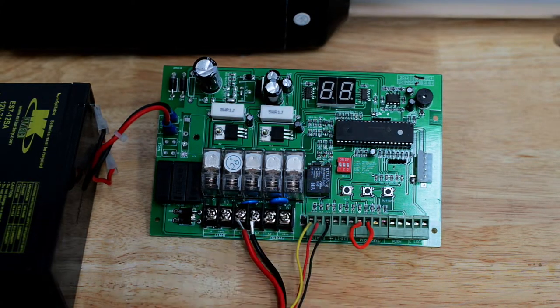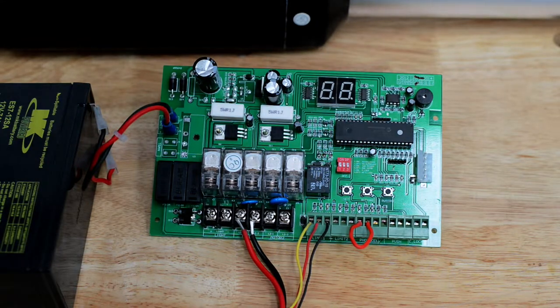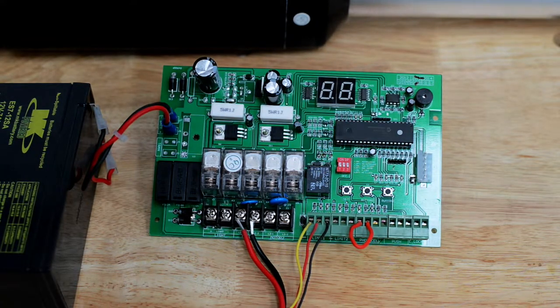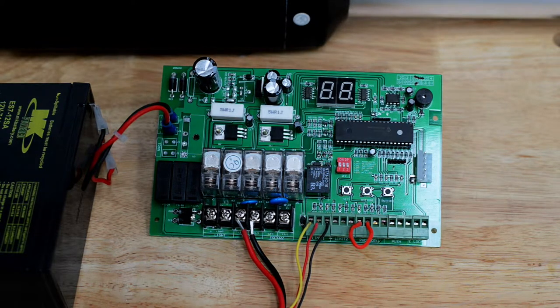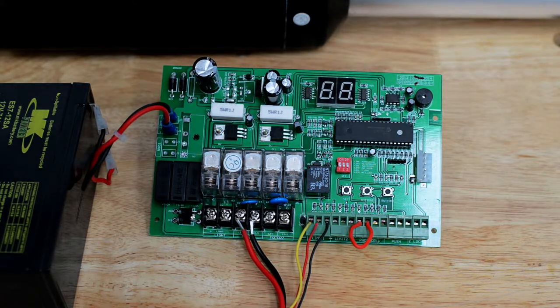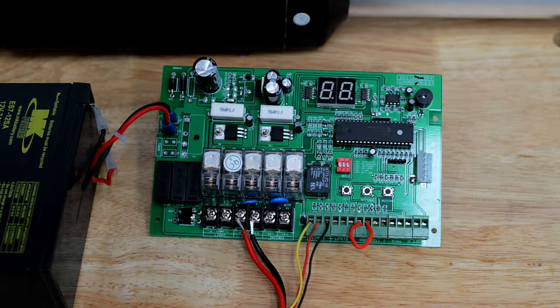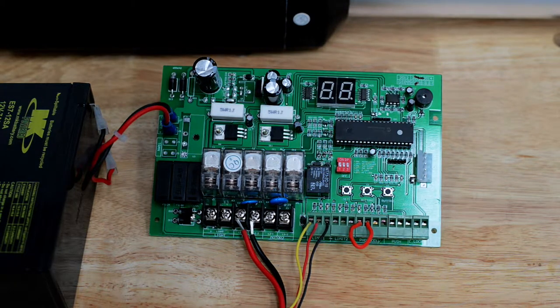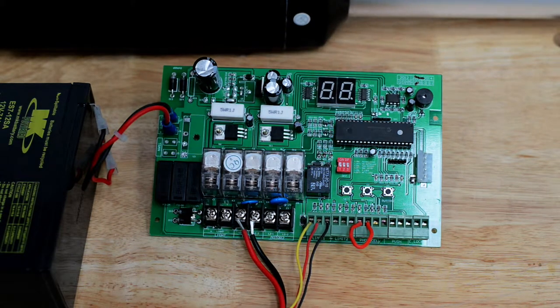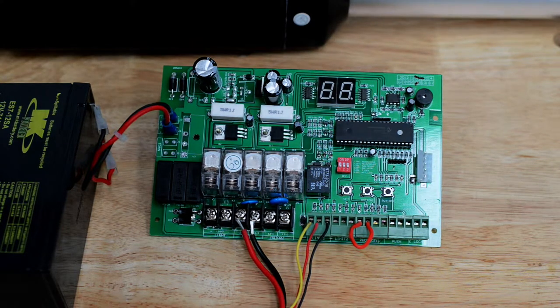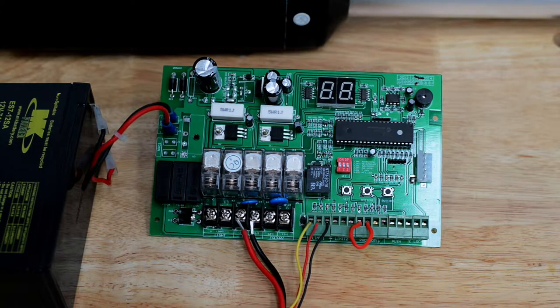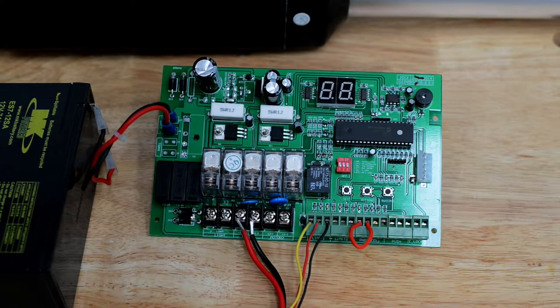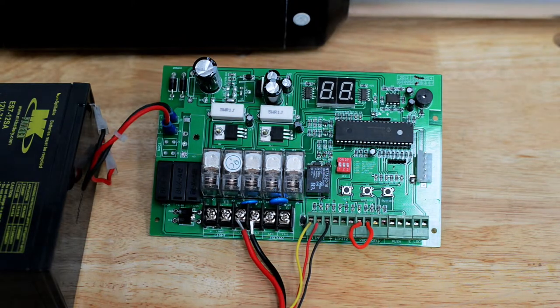The V positive terminal is a power output meant for one accessory. It is not a fused terminal, so do not hook up multiple accessories to that terminal. It puts out 12 volts DC. The 4th terminal positive 12 volt is also a power output for accessories. However, this is a fused output. This one is safe to hook up the remaining accessories to that you need to get power.